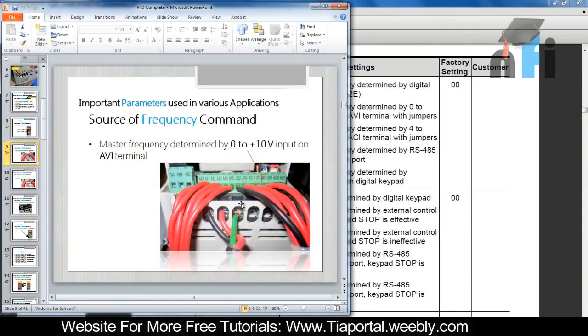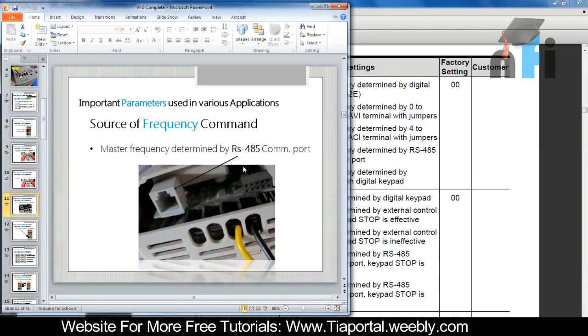So that's how you can change the frequency - we have five modes. First was from the keypad: increment and decrement to change the speed. Second was from AVI terminal: 0 to 10 volts. Third was ACI terminal: analog current input 4 to 20 mA, which is quite similar to AVI but using current. Fourth was RS-485 communication Modbus mode - the video is already available. The last one was the potentiometer on the digital keypad to read and set the speed. That was all about source of frequency commands in the drive.